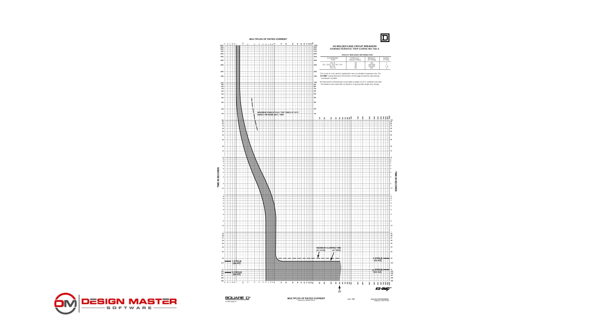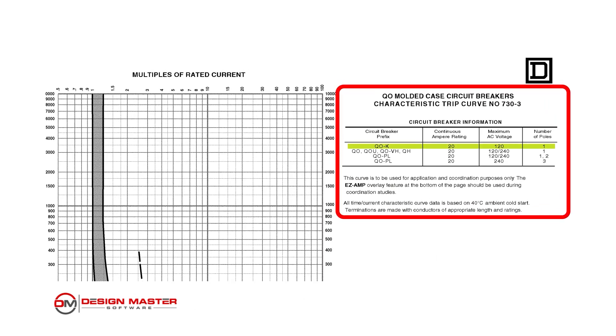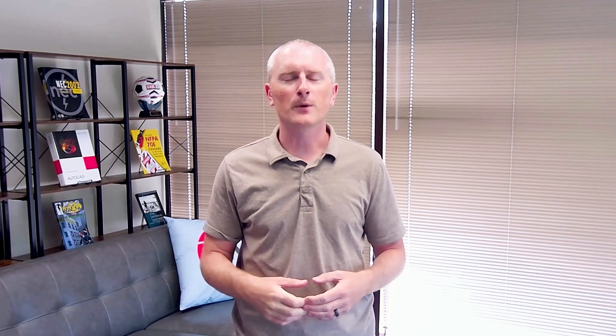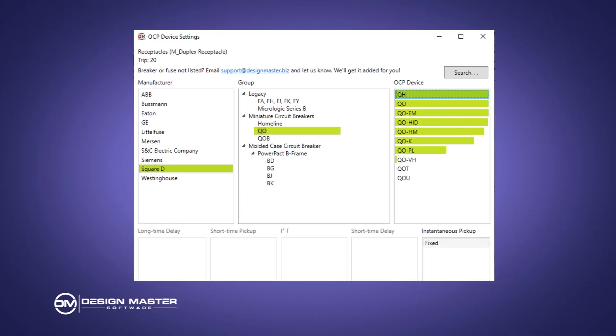That said, a lot of the curves are actually duplicates. A breaker will have many different settings that don't impact the trip, and a manufacturer will publish a single trip curve corresponding to 10 different types of breakers. In our software we list each of those types separately so you can choose the specific breaker you're using — that way you can be certain you've got the right one, since sometimes they do subtly change. But know that sometimes it doesn't actually matter all that much.